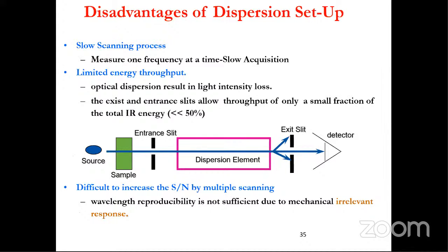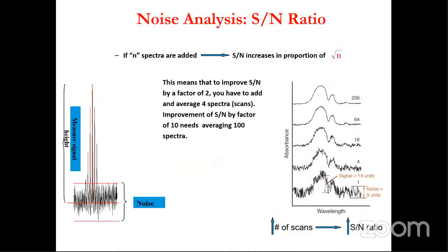So this is the dispersive spectrometer. It is a slow scanning process that measures only one frequency at a time, so acquisition is slow. It has limited energy throughput, and optical dispersion results in light intensity loss. So they are not being used as of now; they are obsolete. So what is the noise level? It depends on the number of scans you are doing, and each scan has a certain noise level. So we have to increase the number of scans so that the S/N ratio is improved.